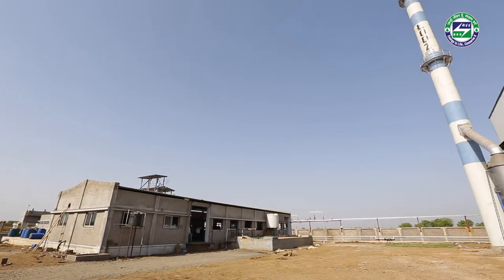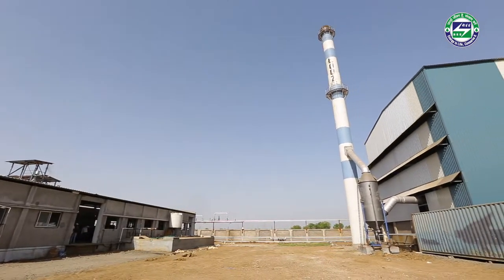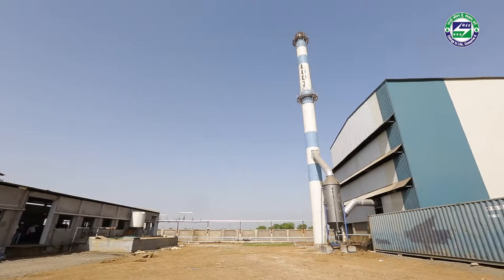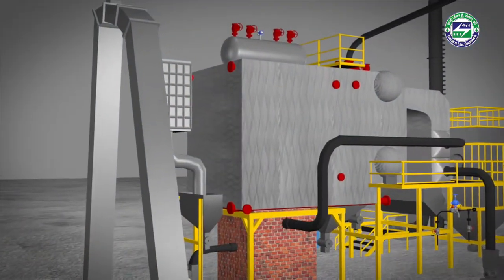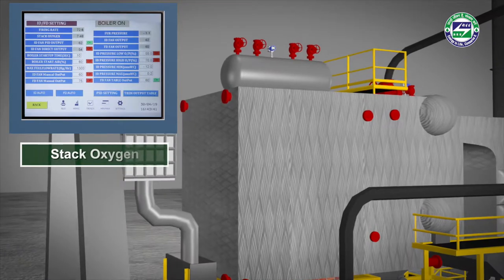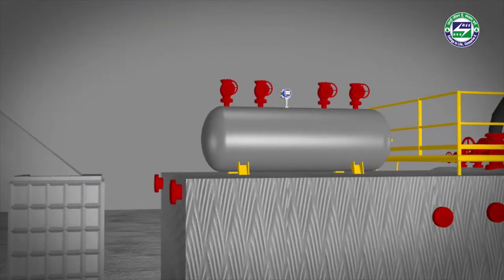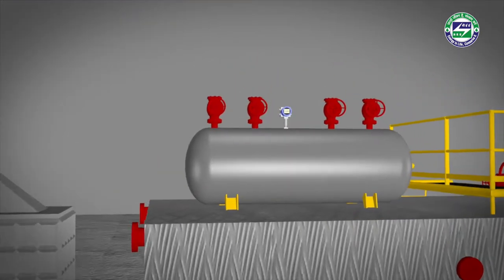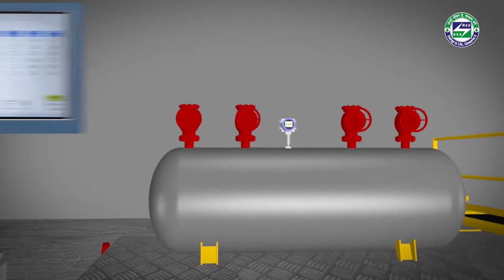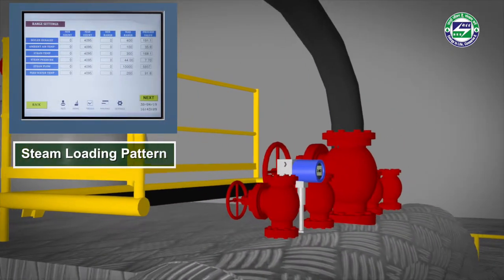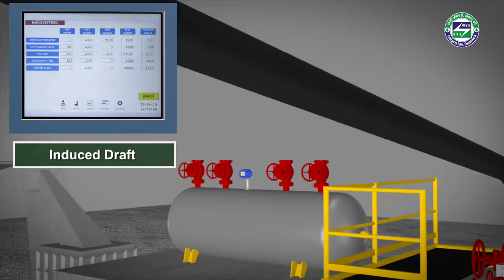The improved system cuts down stack loss by trimming excess air in flue gas through IDFD control automation based on furnace pressure, stack oxygen, and boiler load. It reduces unburnt loss by optimizing fuel feed rate and analyzing steam loading patterns, stack oxygen level, and induced draft.